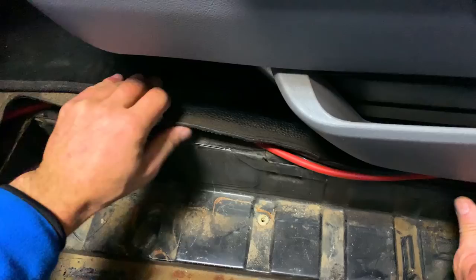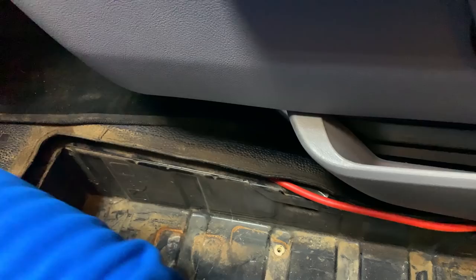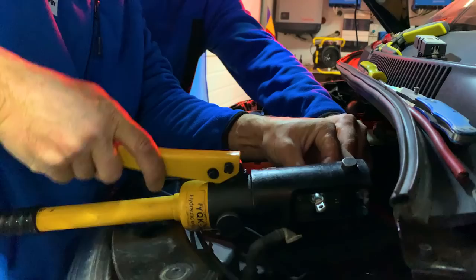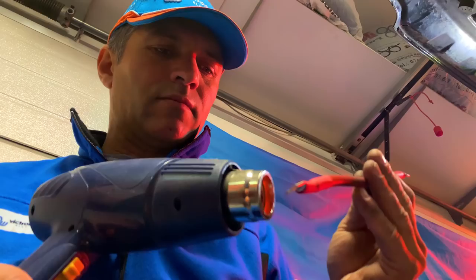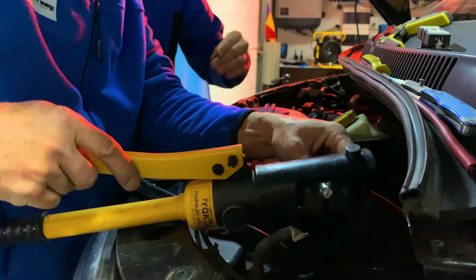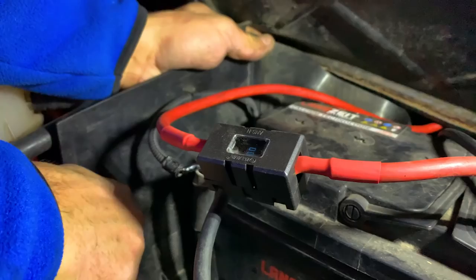In this install, to avoid the need for a secondary conduit, the engineers use double-insulated cables: red for positive and black for negative. Correctly sized eyelet terminals were fitted to the cable ends and covered with heat shrink.